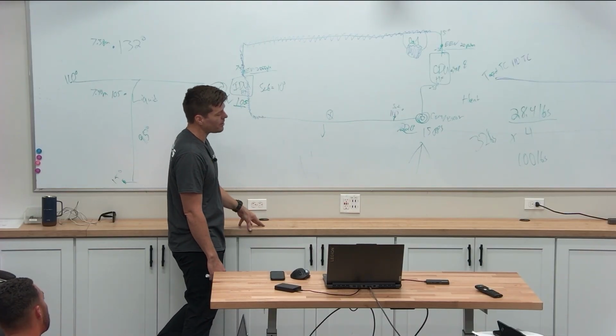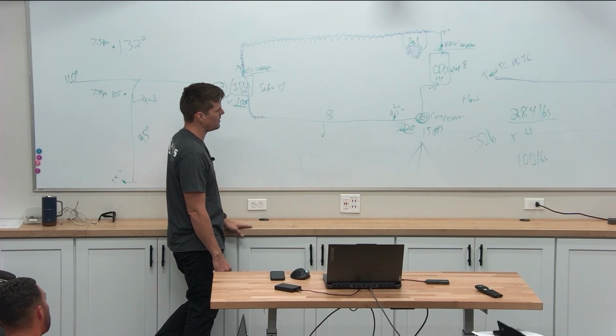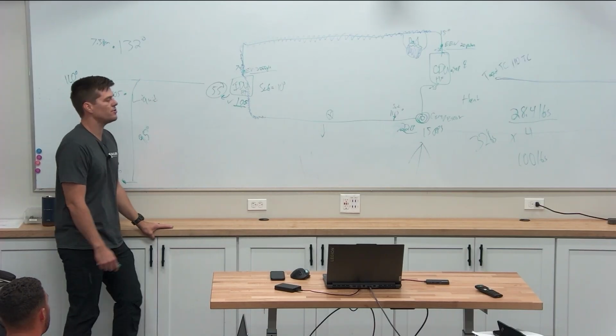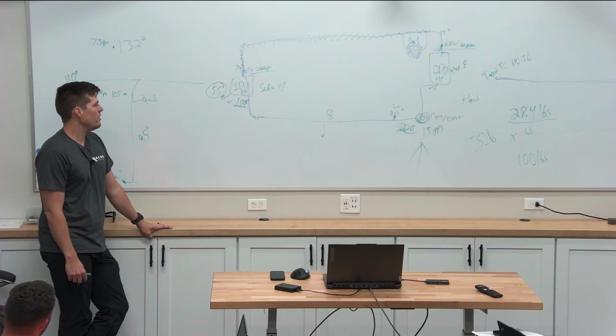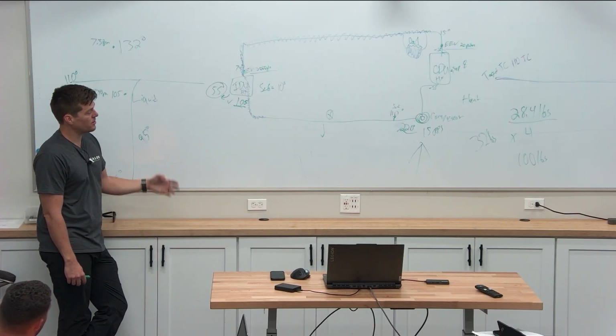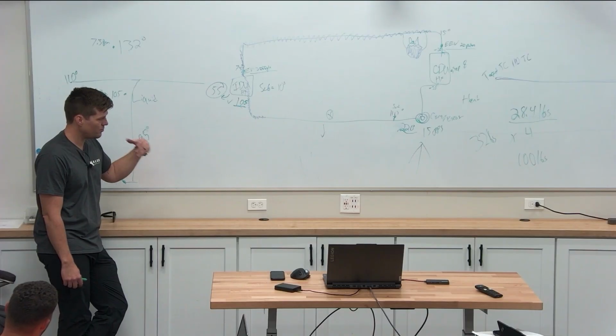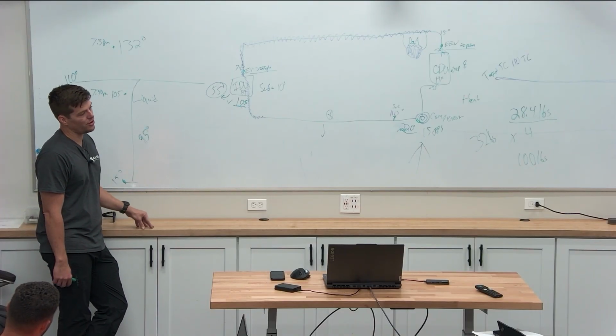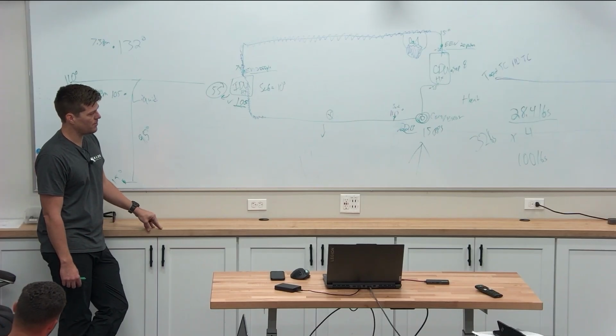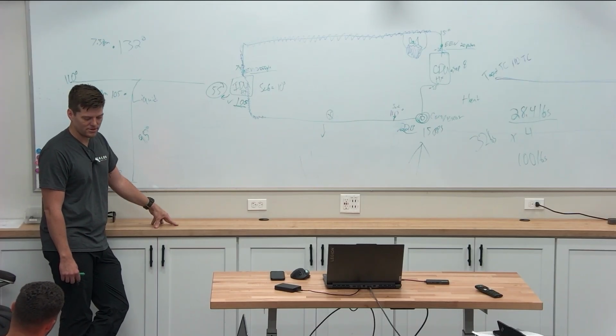We could pull it out in increments, but remember, 410A is a blended gas, so there's no telling what mixture we leave in and what percentage is left. We recommend we just recalculate the line set length, right? Do the right math, and then add the right charge after we pull the charge. And we pull the charge, and they only sent you to the job with a 50-pound recovery tank.